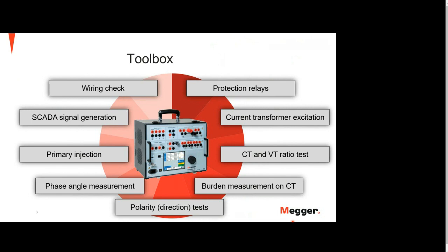We can do phase angle measurements with the Sverker 900, measuring directly from the switchgear, for example, between one voltage and one current. We can do polarity tests when we are testing voltage transformers and current transformers. Also burden measurement and ratio test with current transformers and voltage transformers. Also, we can do the CT magnetization test on the current transformer to find out the voltage knee point, for example. But of course, we can also do protection relay tests. So actually, that's the main function of the Sverker 900, but not the only function. So Sverker 900 can do a lot in the substation.